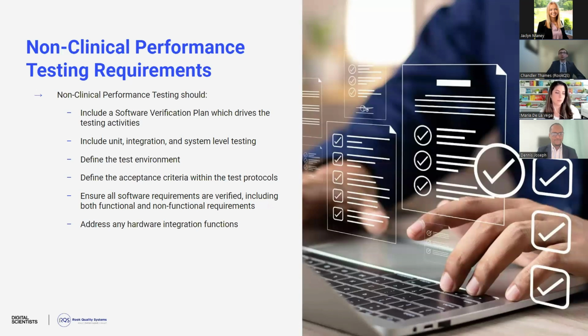So that software verification plan really should tackle all of your software requirements that you've defined, whether device specific or system specific, backend, all of those things are relevant to the software requirements and testing reports. And it should also address any hardware integration functions. So even if your device is a standalone software as a medical device, if it's integrating or pulling data from any hardware or medical devices, even if that's not your device itself, you need to make sure that the integration is covered as well, making sure that the data is able to pass back and forth as necessary and that there's no risk being introduced from that hardware integration.